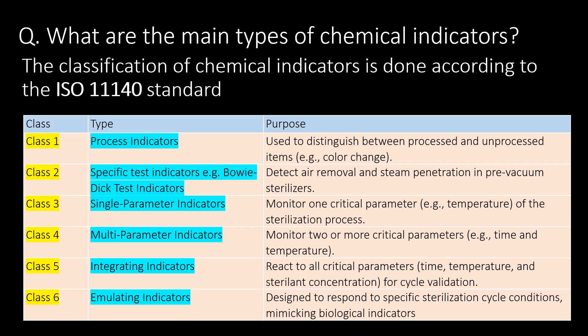What are the main types of chemical indicators? The classification of chemical indicators is done according to the ISO 11140 standard as follows: Class 1 process indicators; Class 2 specific test indicators, example Bowie-Dick test indicator; Class 3 single parameter indicators; Class 4 multi-parameter indicators; Class 5 integrating indicators; and Class 6 emulating indicators.